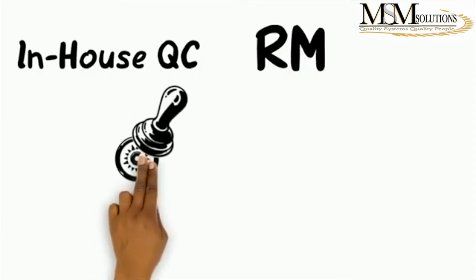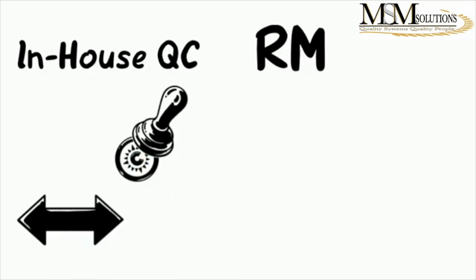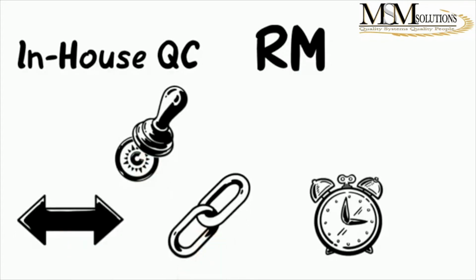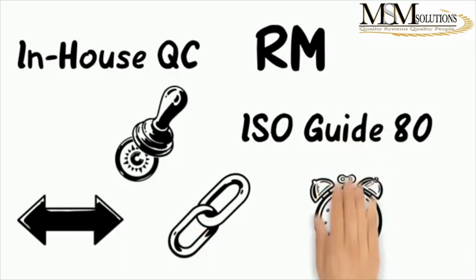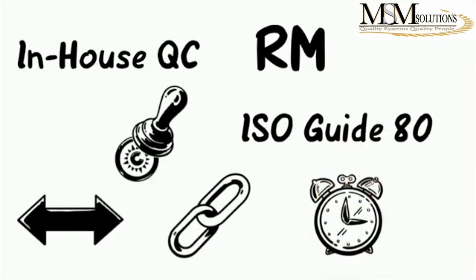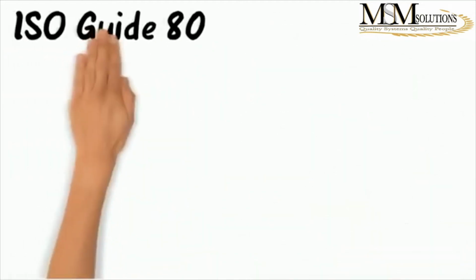However, even if we use our own in-house, we prepare our own reference material, we need to ensure that it still complies with the basic requirements of a reference material, meaning it needs to be homogeneous and it needs to be stable for a long time. There is a preparation guide, ISO Guide 80, that can actually help in making sure that the in-house prepared QC meets all these requirements.